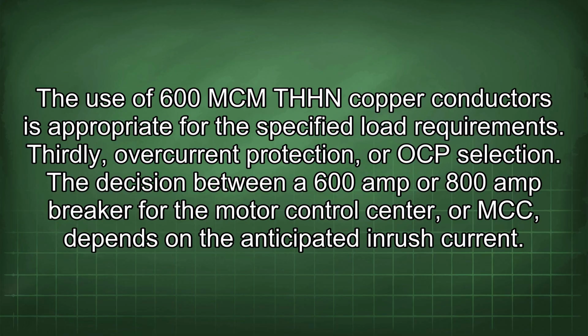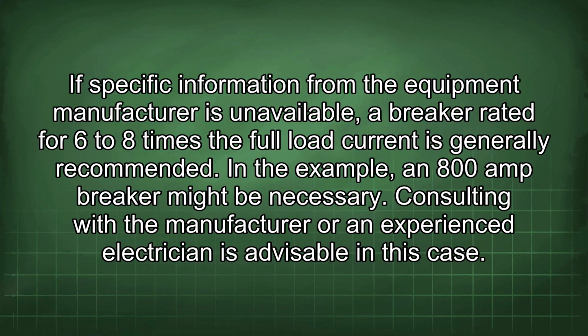Thirdly, overcurrent protection, or OCP selection. The decision between a 600 amp or 800 amp breaker for the motor control center, or MCC, depends on the anticipated inrush current. If specific information from the equipment manufacturer is unavailable, a breaker rated for 6 to 8 times the full load current is generally recommended. In the example, an 800 amp breaker might be necessary. Consulting with the manufacturer or an experienced electrician is advisable in this case.